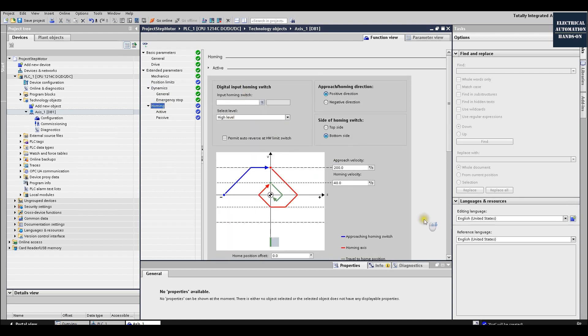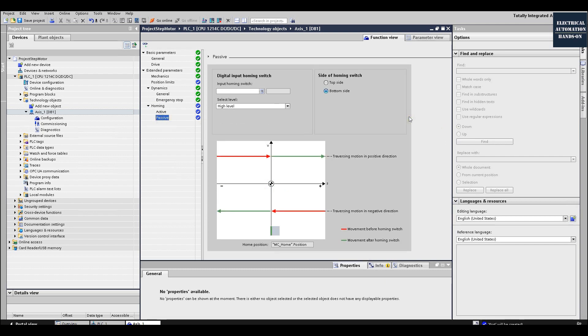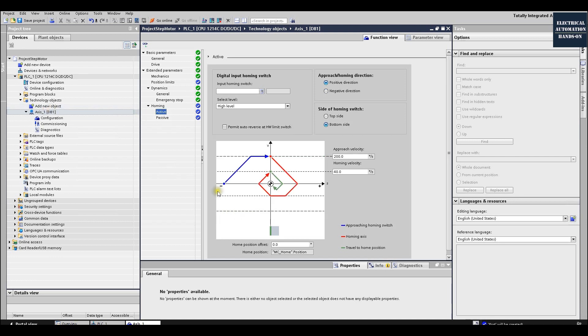Homing is a big topic I've covered in other videos. Typically we use the passive method — a simple way where you move the drive to a certain position and set it as the target value (typically zero). For active homing, your system has a home switch: control the motor to run back toward the home sensor, and once it touches the sensor, it slows down, runs backward, touches the sensor again, and through this sequence finds the home position very accurately and consistently. Then set a target home position value to the axis.